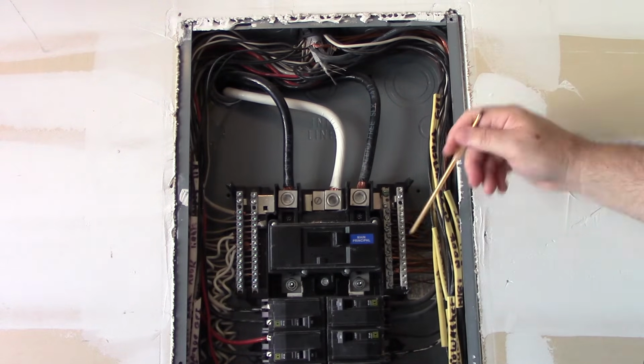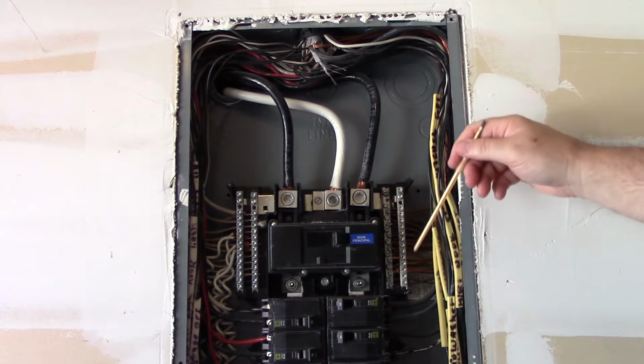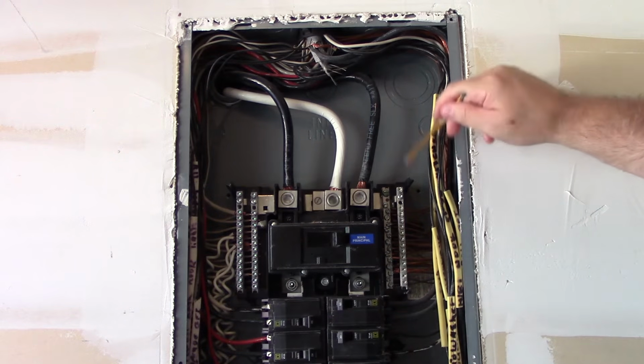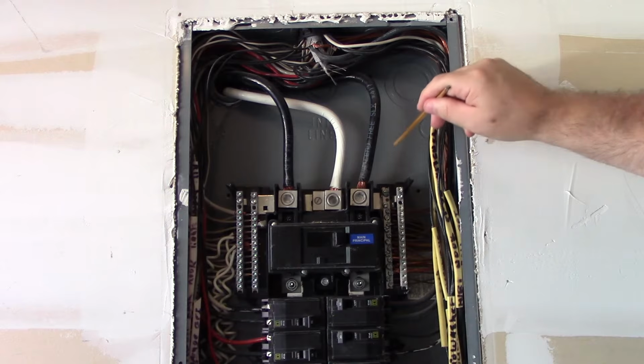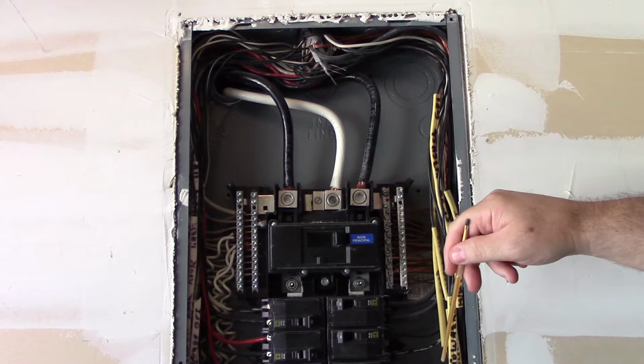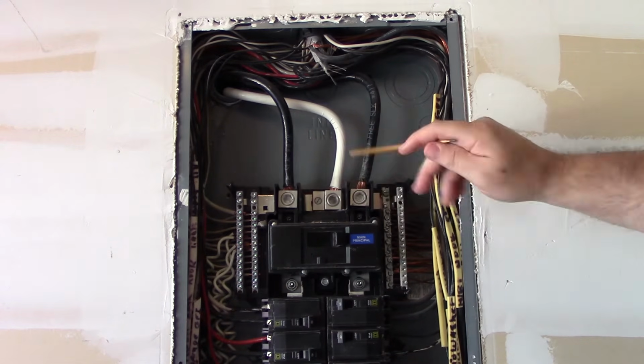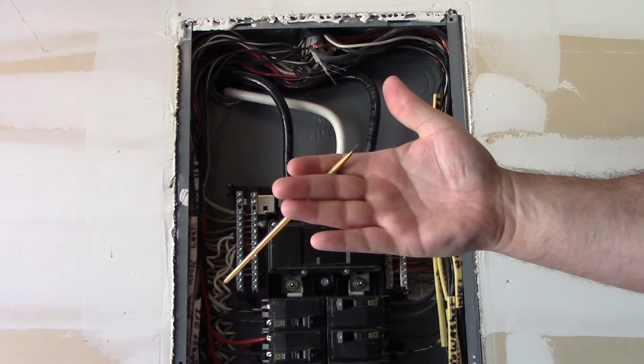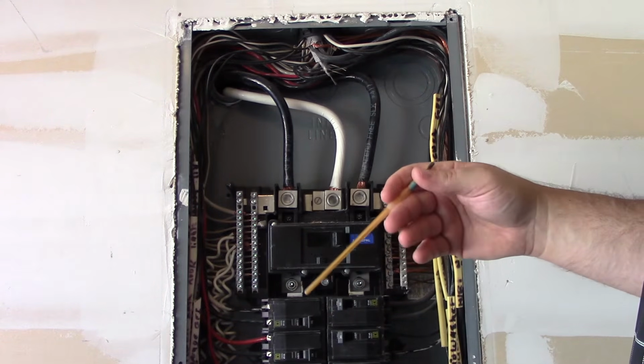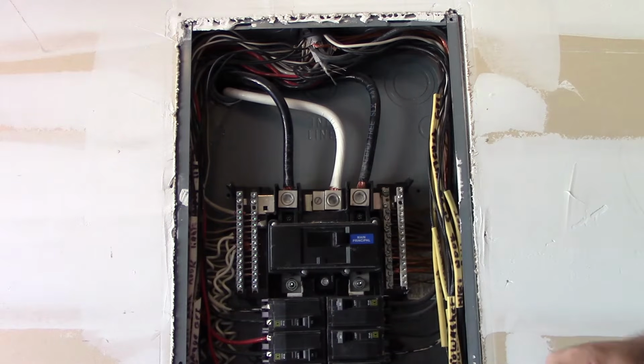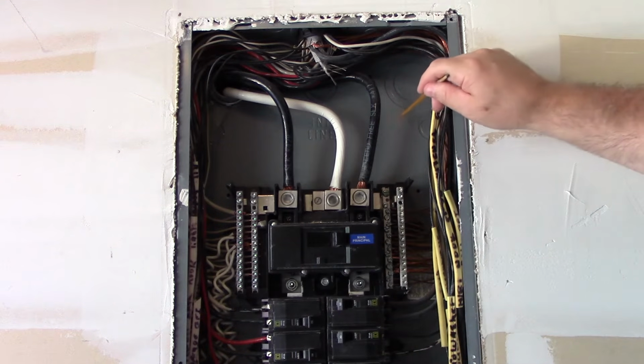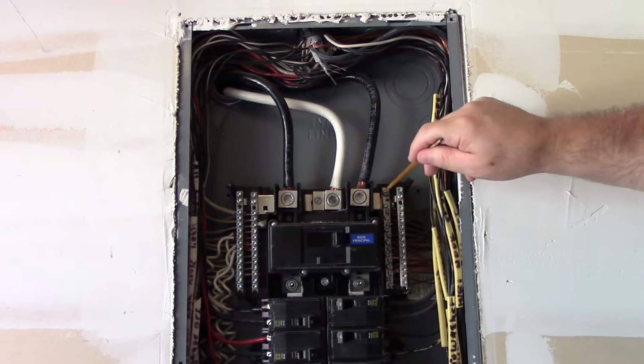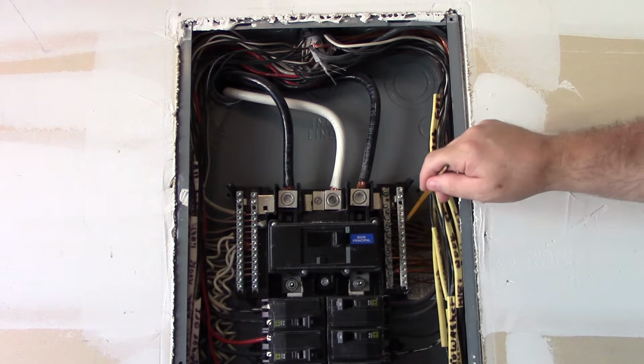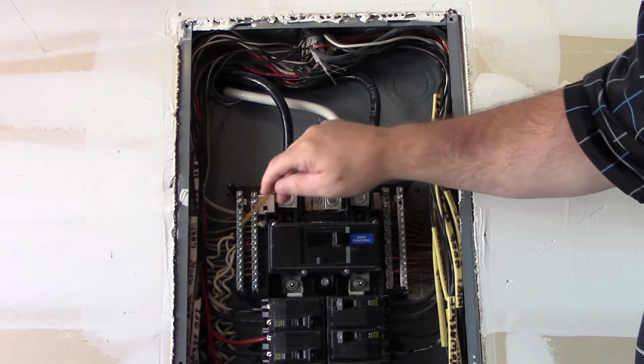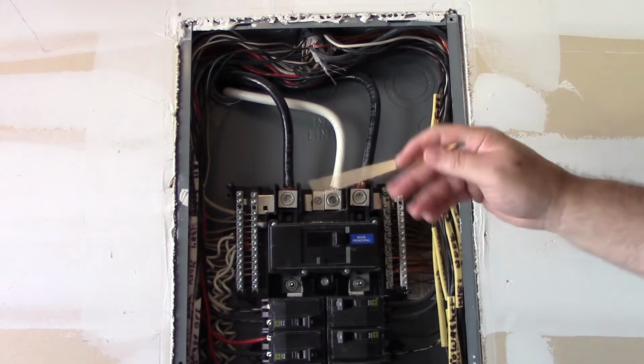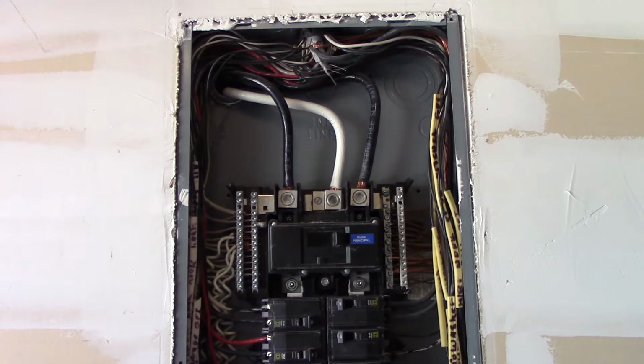All right, so what you want on a remote distribution panel is you want the equipment grounding conductors connected to the cabinet and to your grounding electrode system. Whereas you want your neutrals to be isolated away from the cabinet. In a service panel, that's totally different. You want it all to be the same. I want the cabinet connected to the bar by that main bonding jumper. My equipment grounding conductors terminate on the same bar. My grounded conductors terminate on the same bar, all together. Not the same in a remote distribution panel.